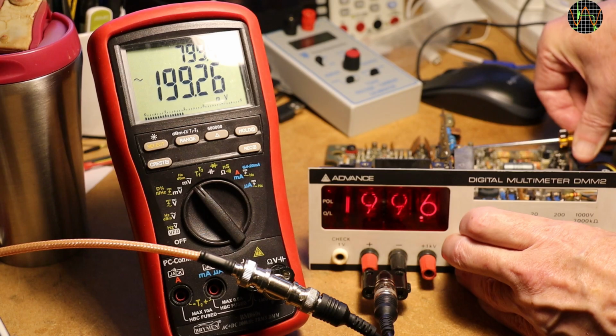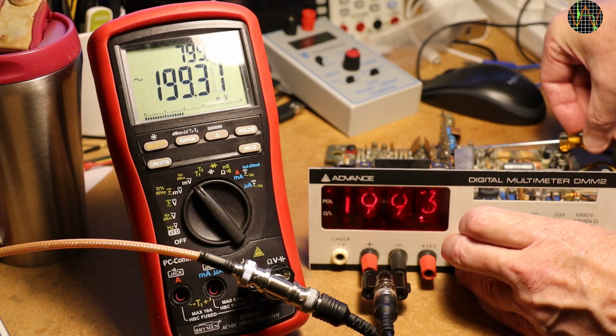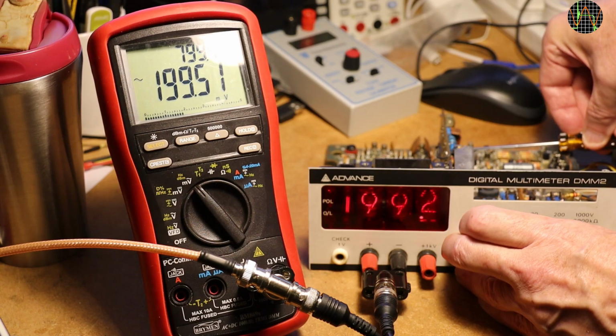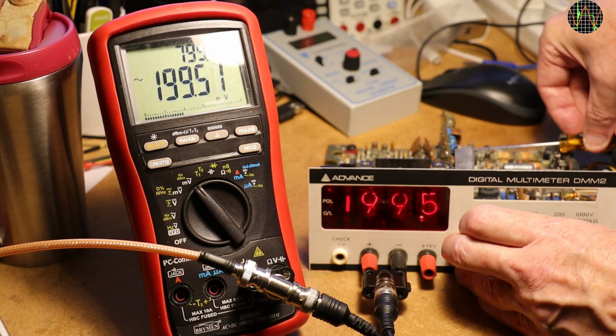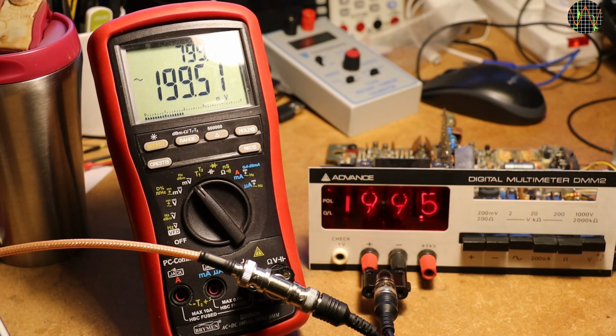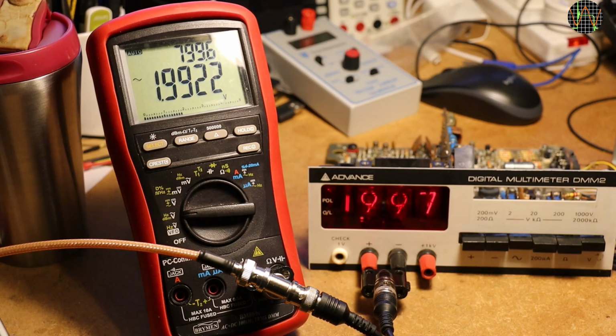This is followed by adjusting the 200 mV AC range with a 199 mV AC signal at 800 Hz. Actually, the step before that was shorting the input and setting AC 200 mV to 0. I did not show that because it was already set. Now for the same but at 1.999 volts. I think this is good enough. Actually, there are 3 more steps to adjust AC at 20 kHz, which I did but skip here.